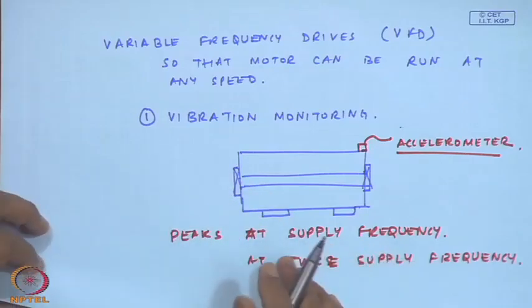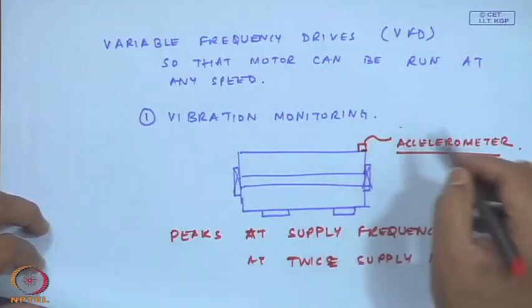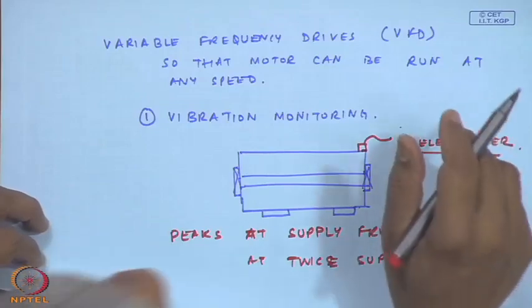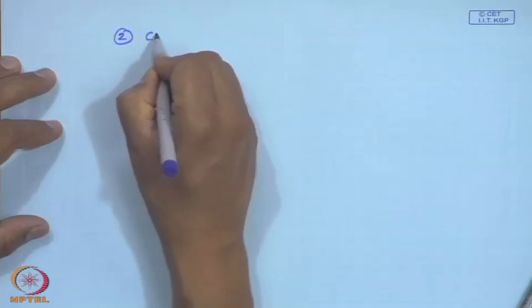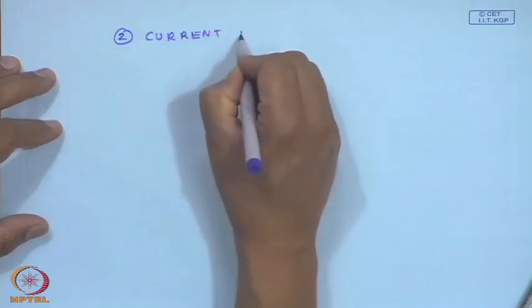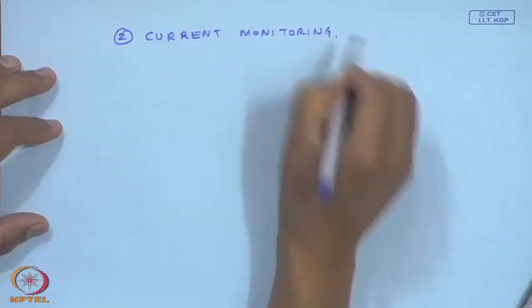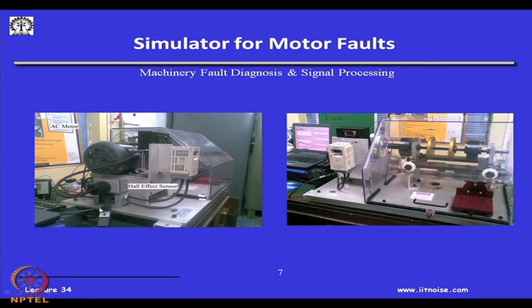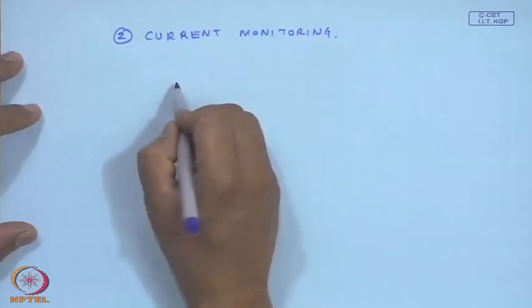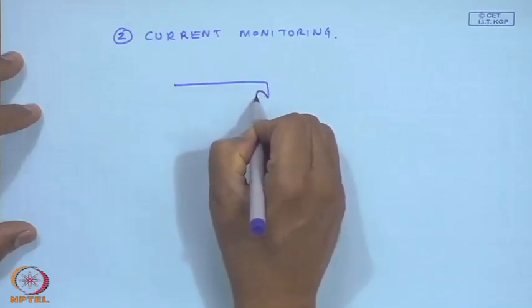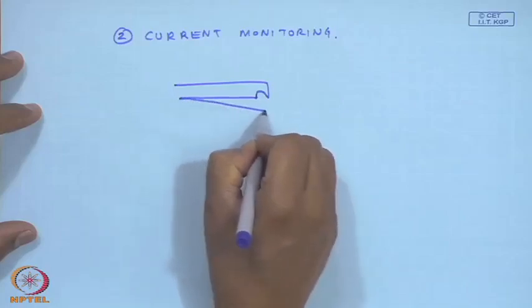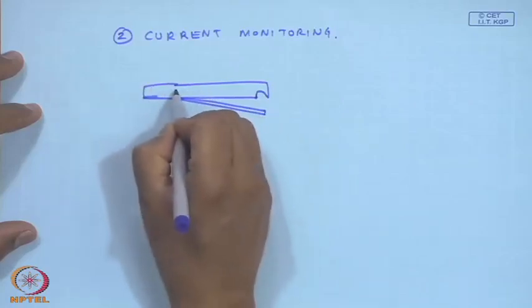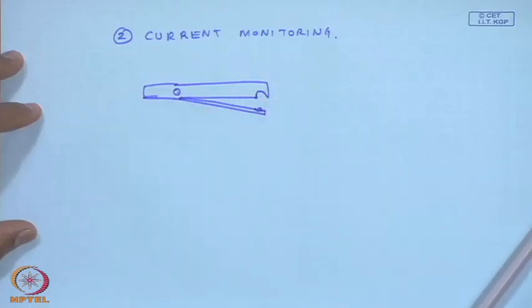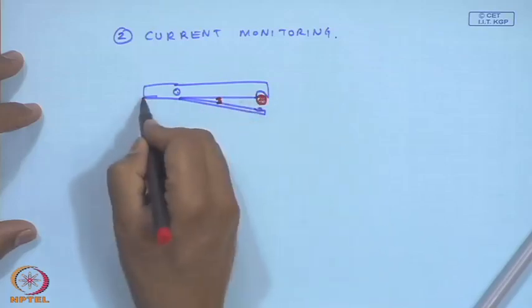We can do vibration monitoring, but in this class, since you already know what vibration monitoring is, and all you do is put a vibration sensor close to the bearings of the motor, record the time history, and then do an FFT. But we can also very easily monitor through what is known as current monitoring. Okay, and in this experiment, to measure the current, we are actually using a Hall effect sensor here. If you can see, the sensor is like a clamp on a conductor, basically something like this. So, this is like a spring loaded thing, and the conductor will actually come here.